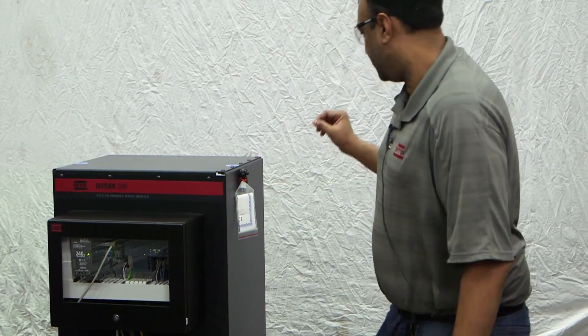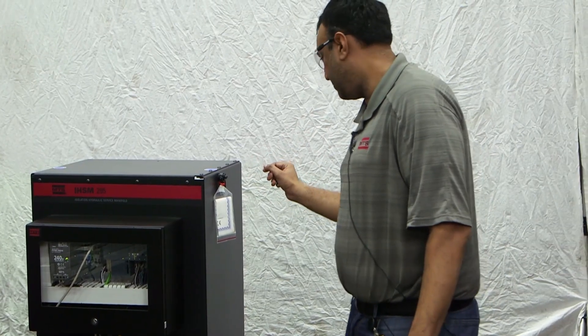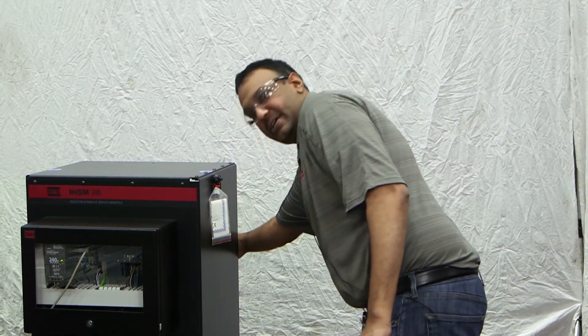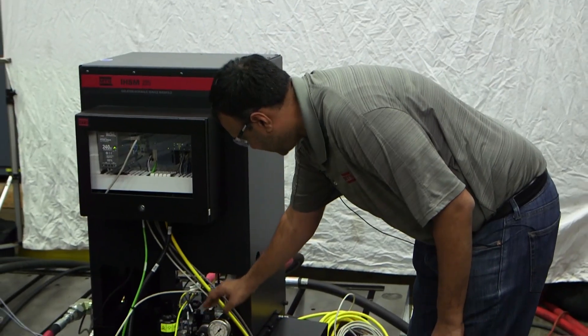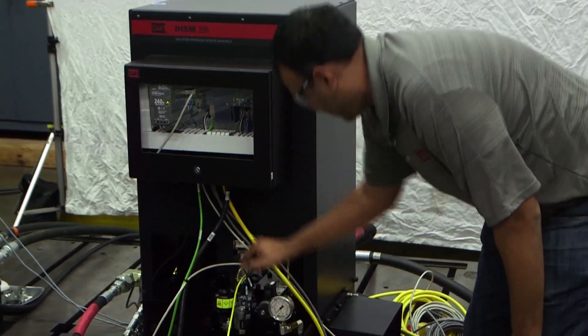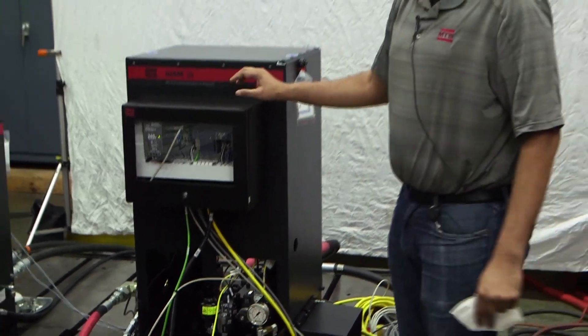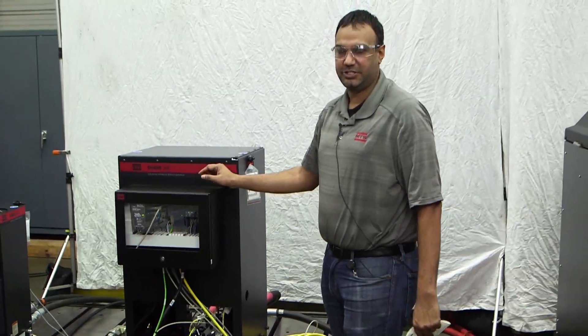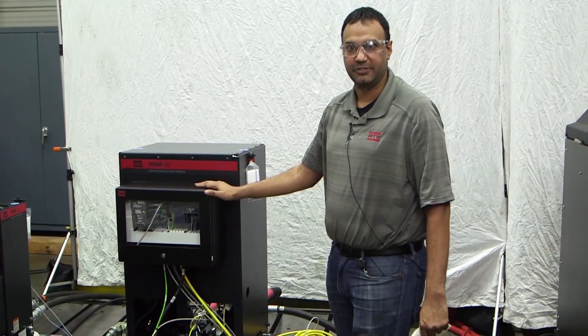The dirty filter and the incoming pressure switch are on the back side. All the valves and the valve feedbacks are right here. The two valves that have feedback, one here and one here, give us the safety rating we need to achieve PLD or PLE for this system.